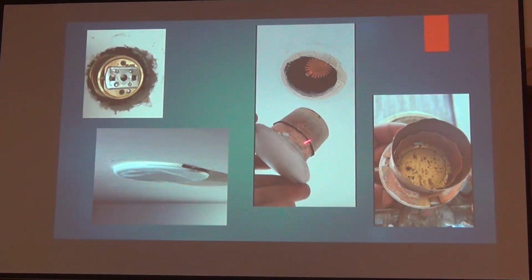Okay, this is not allowed. That's that deflector that I showed you that drops down. That's clearly not going to do anything but spray water above the ceiling. Painters like to caulk gaps. That gap I need. Plus, it wouldn't let the cover drop off.